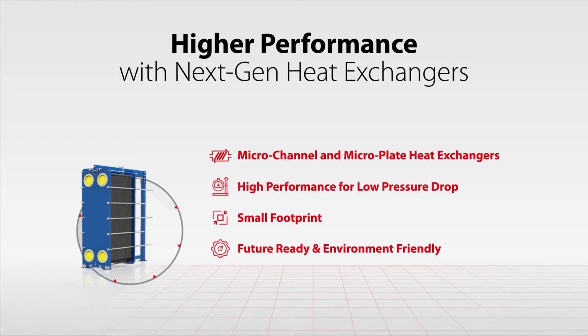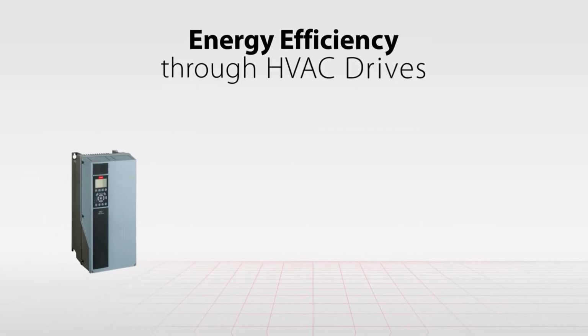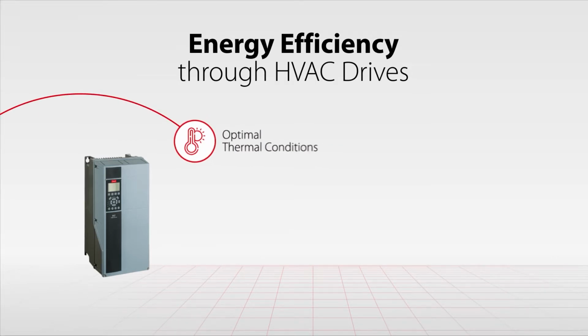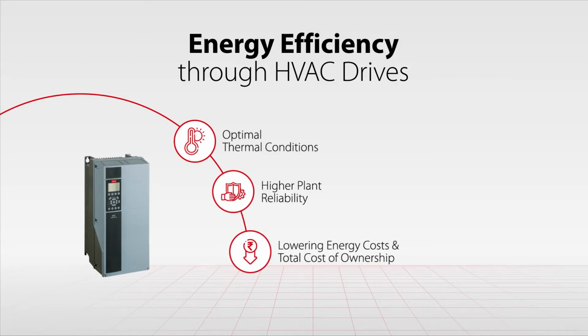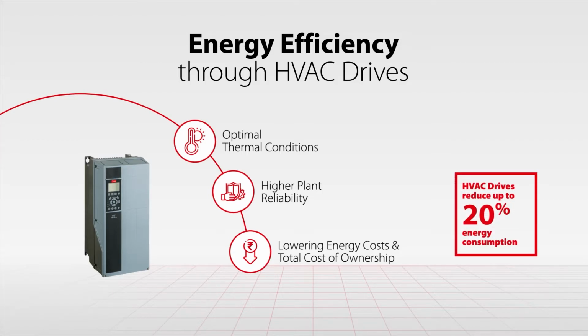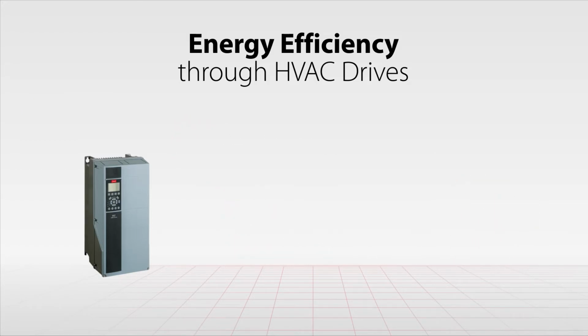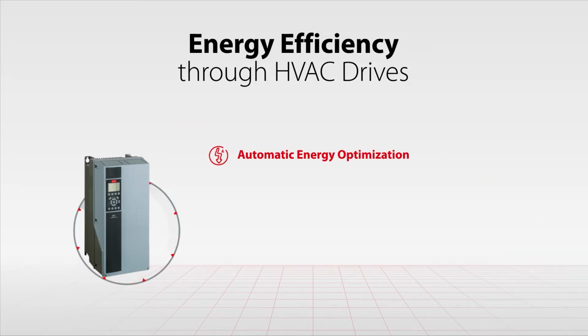They further aid in adhering to legal regulations as well as obtaining environmental certifications and green tax incentives for the future. Danfoss HVAC drives for data centers ensure optimal thermal conditions, offer higher plant reliability, while lowering energy costs as well as total cost of ownership, which result in higher performance of IT equipment in data centers. Danfoss HVAC drives offer up to 20% lower energy consumption. Drives enable automatic energy optimization that reduces current and voltage during operation, saving an additional 3 to 5% of energy.